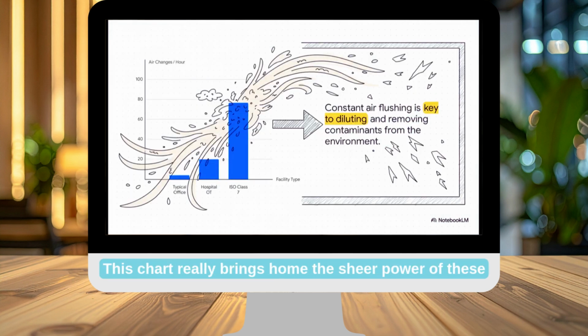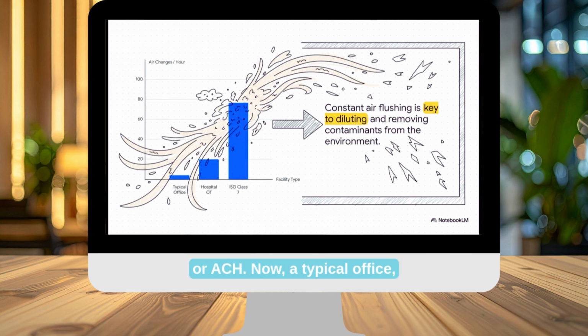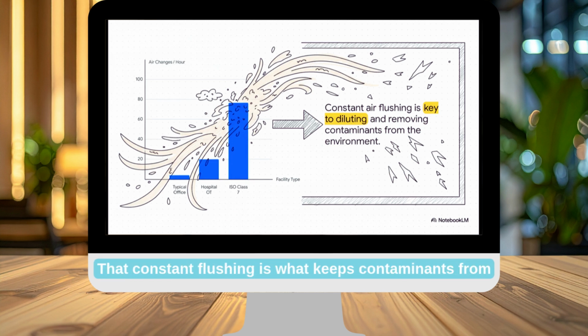This chart really brings home the sheer power of these systems. We're looking at air changes per hour, or ACH. A typical office swaps out its air about 4 times an hour. A hospital operating theater, we're up to 20 times. But an ISO 7 cleanroom, a staggering 60 times an hour. That's a full air replacement every single minute. That constant flushing is what keeps contaminants from ever building up.